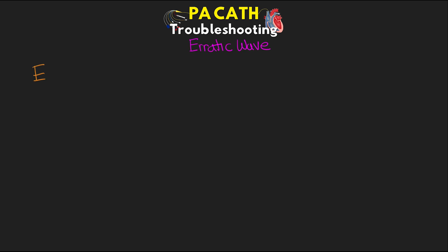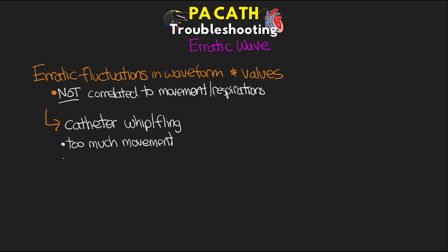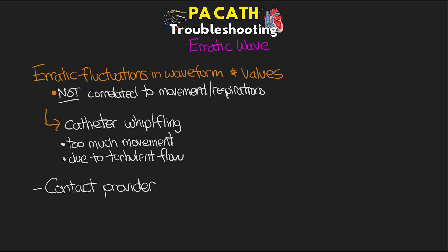The next troubleshooting scenario is if you notice that your patient has an erratic waveform with highly variable pressure, especially if not correlated with movement or respirations. This is probably the result of catheter whip or catheter fling, where the catheter is moving too much in the blood vessel, typically caused by a turbulent area of flow where the catheter is sitting. Contact the provider and let them know — they may need to adjust the position to get it away from that area of turbulent flow.